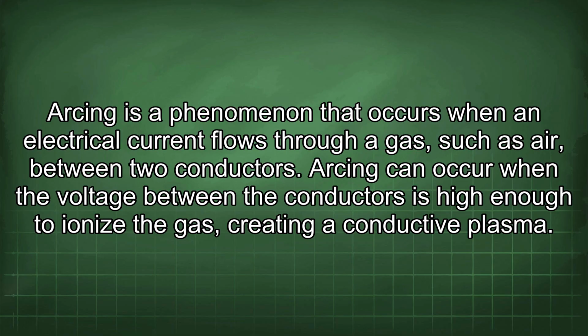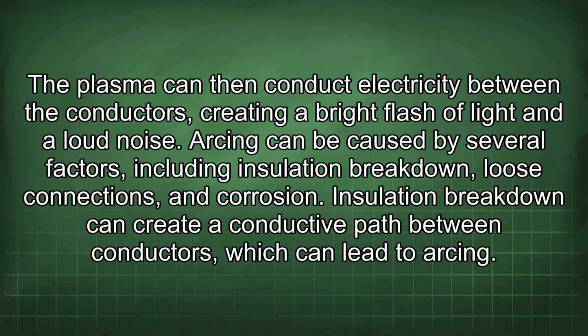Arcing is a phenomenon that occurs when an electrical current flows through a gas, such as air, between two conductors. Arcing can occur when the voltage between the conductors is high enough to ionize the gas, creating a conductive plasma. The plasma can then conduct electricity between the conductors, creating a bright flash of light and a loud noise. Arcing can be caused by several factors, including insulation breakdown, loose connections, and corrosion. Insulation breakdown can create a conductive path between conductors, which can lead to arcing.